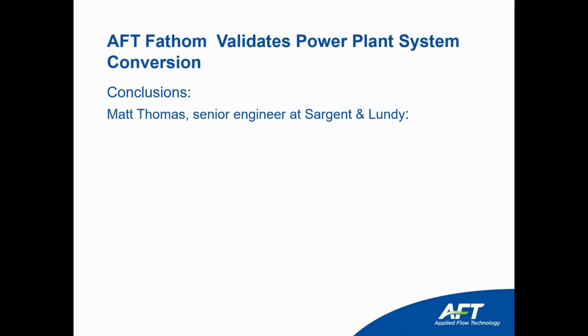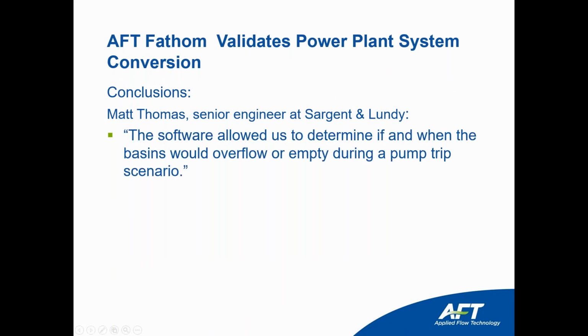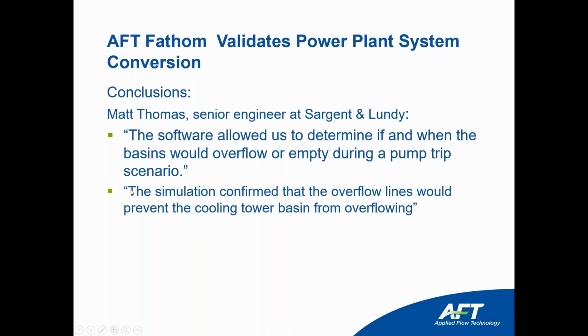So we saw the results of the graph. This was the CT, the cooling tower pump trip, and also the cooling water pump trip. We looked at the graph to make sure that it didn't overflow during the whole operation. So the conclusions of this work, Matt Thomas, senior engineer from Sargent & Lundy, is the software allowed us to determine if and when the basins would overflow or empty during the pump trip scenario.